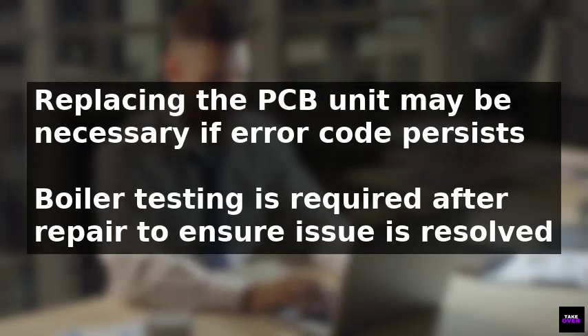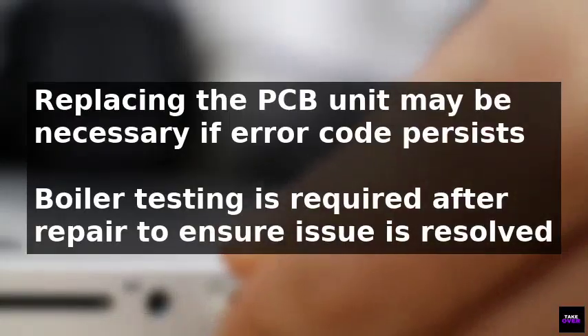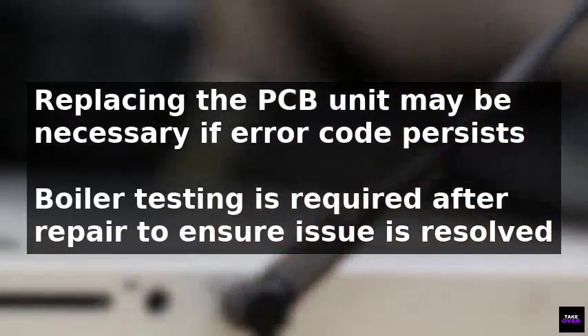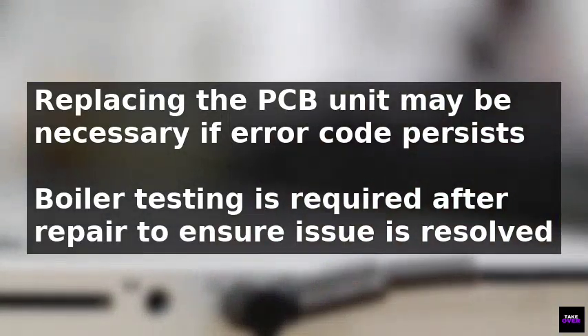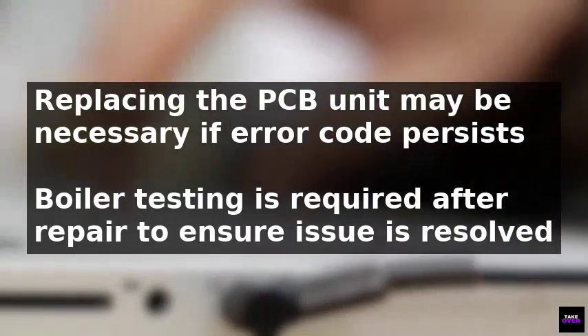After reassembling the appliance and reconnecting the power, the boiler should be tested to ensure the issue is resolved. In some cases, if the error code persists, the technician may need to replace the PCB unit.